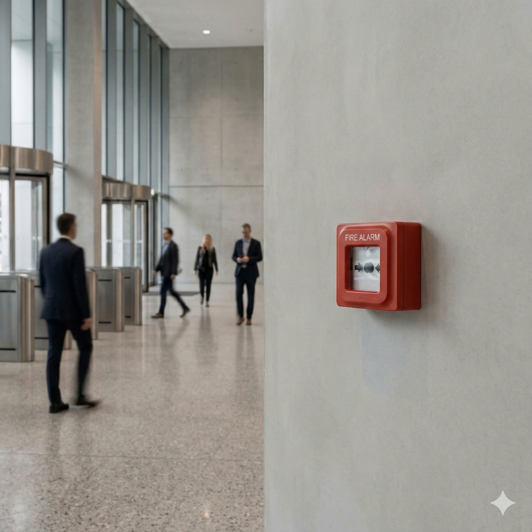We also briefly noted the specific zoning requirements that support the strategy of phased evacuation in high-rise buildings. Right. Phased evacuation is an engineering strategy to prevent catastrophic congestion in stairwells. When a fire is detected, the system doesn't immediately notify the entire building. Instead, it might activate a full alarm on the fire floor, and the floors immediately above and below, but only a supervisory signal on the remaining floors. This enables a controlled, safe, sequenced evacuation, moving people out of immediate danger first.